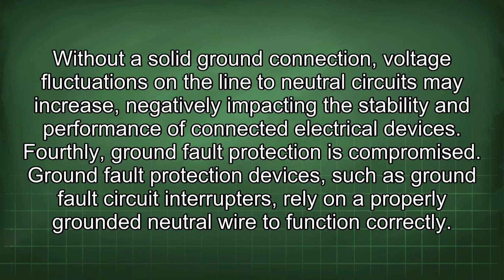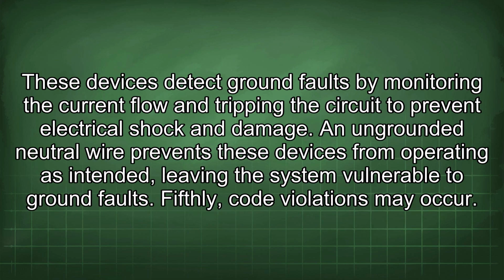Fourthly, ground fault protection is compromised. Ground fault protection devices, such as ground fault circuit interrupters, rely on a properly grounded neutral wire to function correctly. These devices detect ground faults by monitoring the current flow and tripping the circuit to prevent electrical shock and damage. An ungrounded neutral wire prevents these devices from operating as intended, leaving the system vulnerable to ground faults.